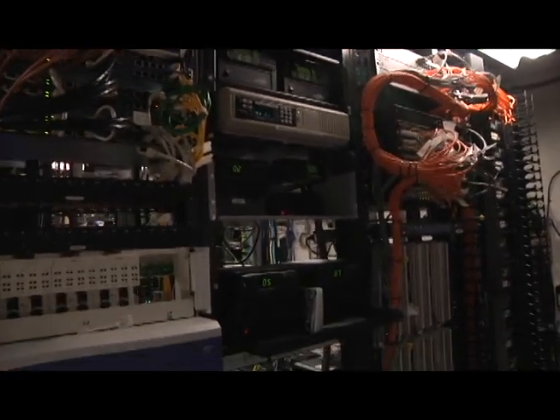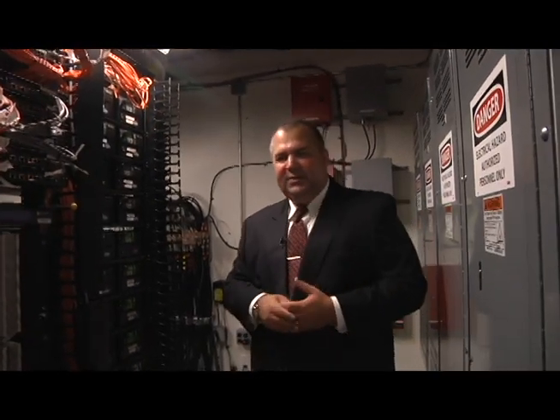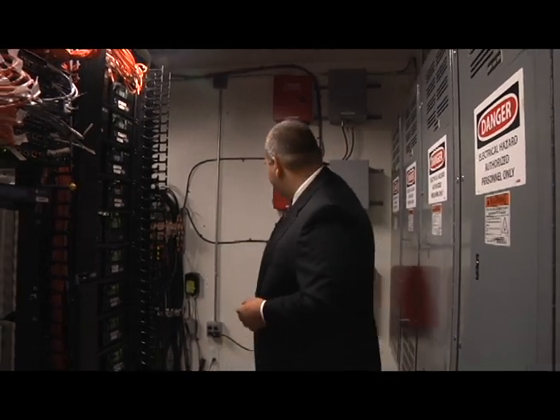And then the UPSs that we had talked about at the beginning of our tour, one of the things that I wanted to mention to you is all of the dispatch positions are, half of them are on one UPS and half of them are on the other UPS. So if we were to have some sort of a failure, we'd only be looking at losing half of our positions. In the server room, we actually have dual power supplies in here. So all of the server equipment, in theory, should never go down because it's being fed from power by both systems.